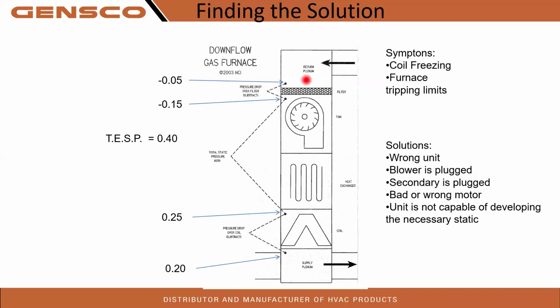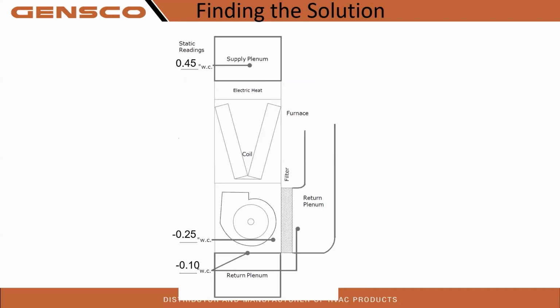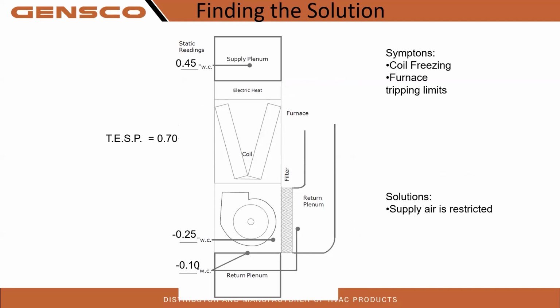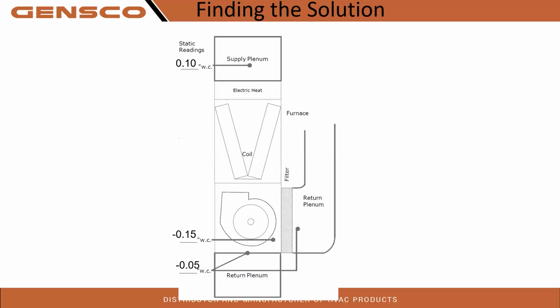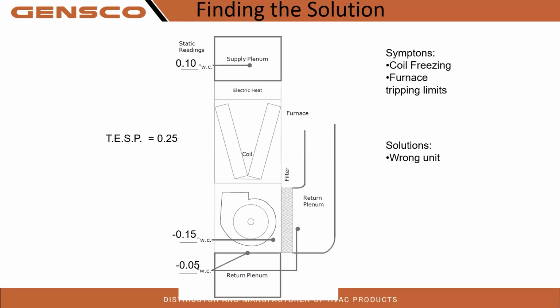So unit, this one, we're under static pressure. Unit's not capable of developing the necessary static. Looks like we got an upflow, total external static 0.7. Our supply plenum's at 0.45. Same thing, coil freezing, furnace tripping limits. We got an over temp. This one, we got our supply air is restricted. What's this one doing? We got 0.05 negative on the return, 0.15, 0.10, not enough air. Total external static pressure 0.25. Same symptoms. Got a wrong unit, undersized.